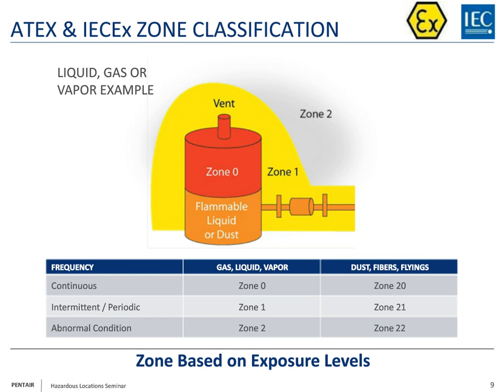So a zone 0 is where you have continuous exposure to hazardous material. So lots of applications here are low power instrumentation that's being installed on a tank to measure the liquid level, for example, of that tank. Zone 1 is where you see more control panel type applications where you have more intermittent or periodic exposure to hazardous material. And then zone 2 is when you have an abnormal condition when that hazardous material is present.